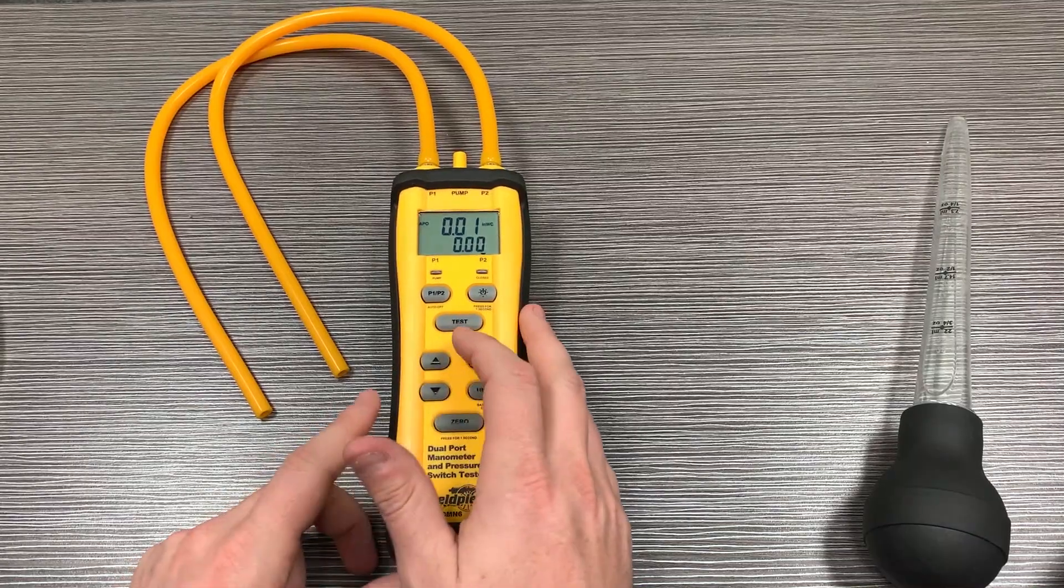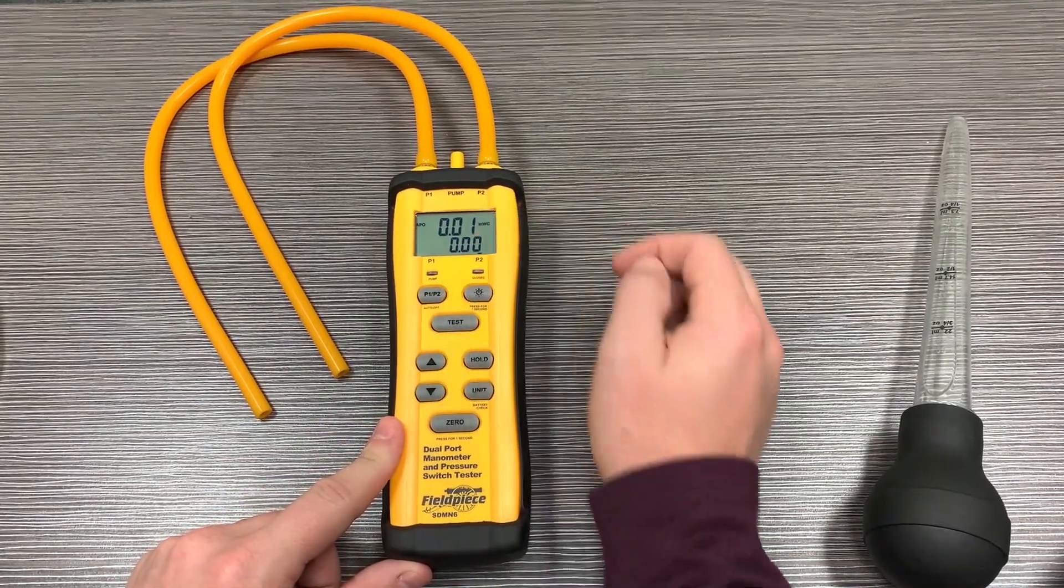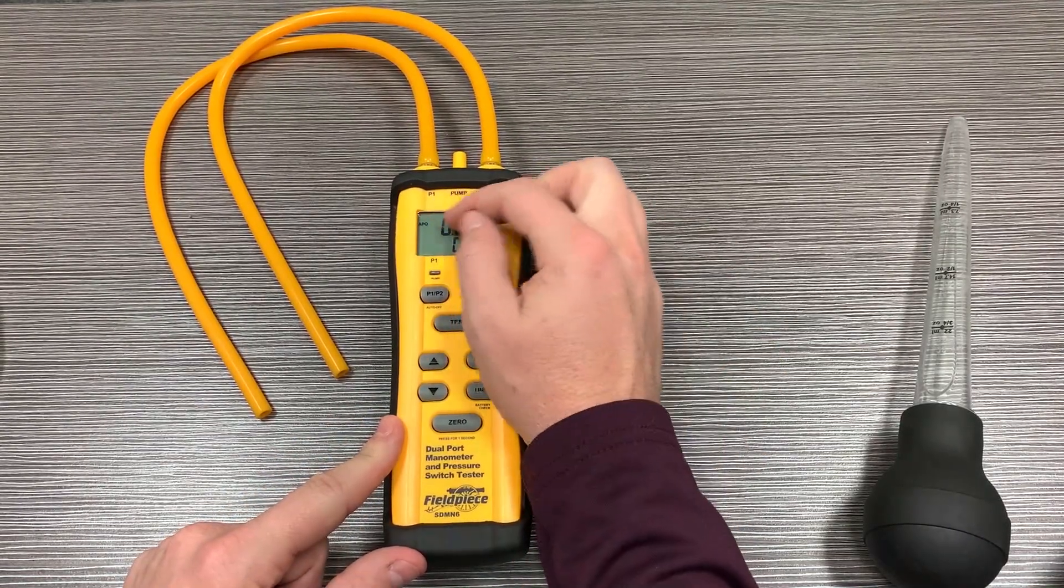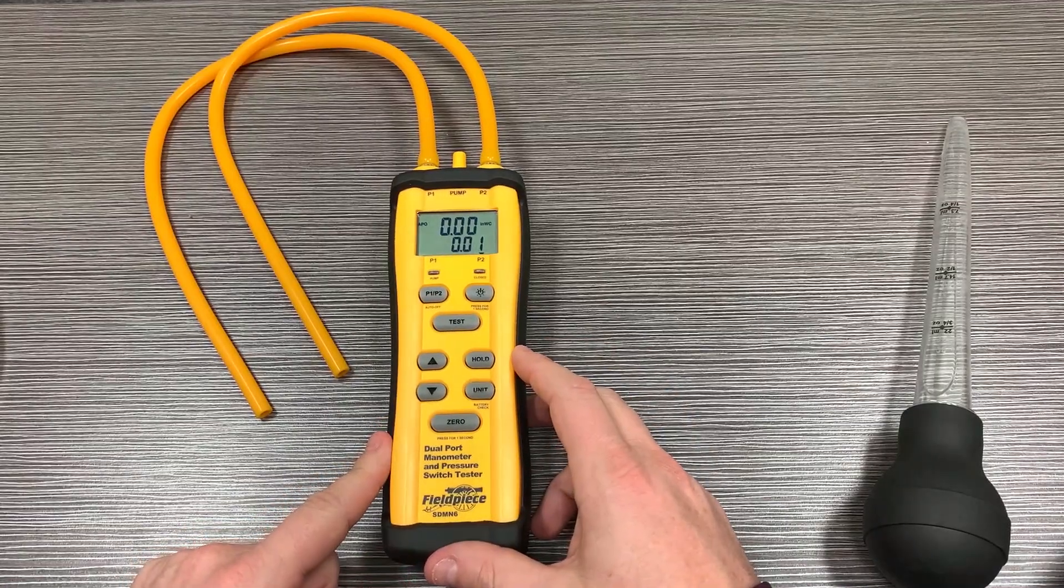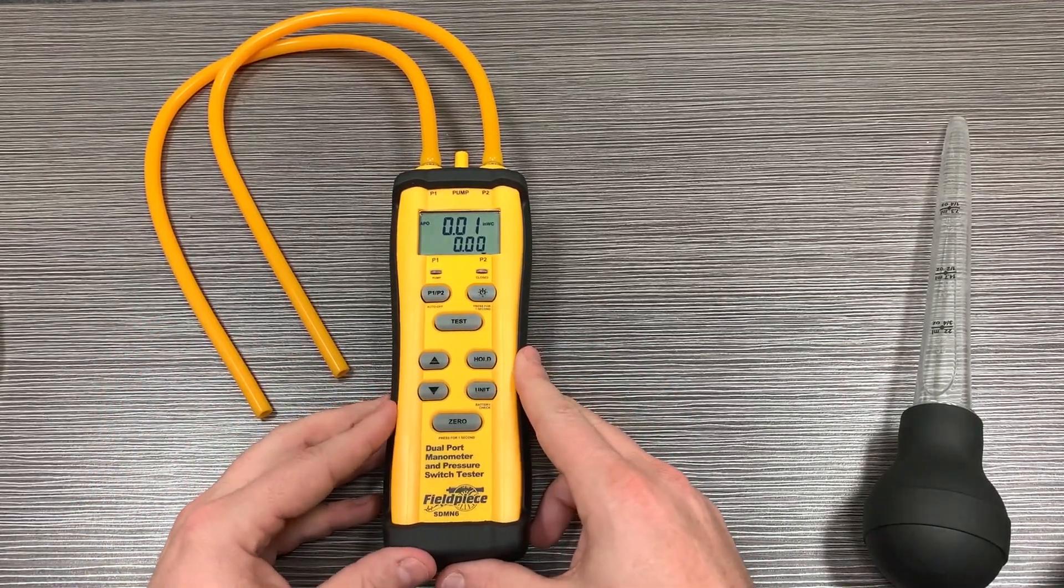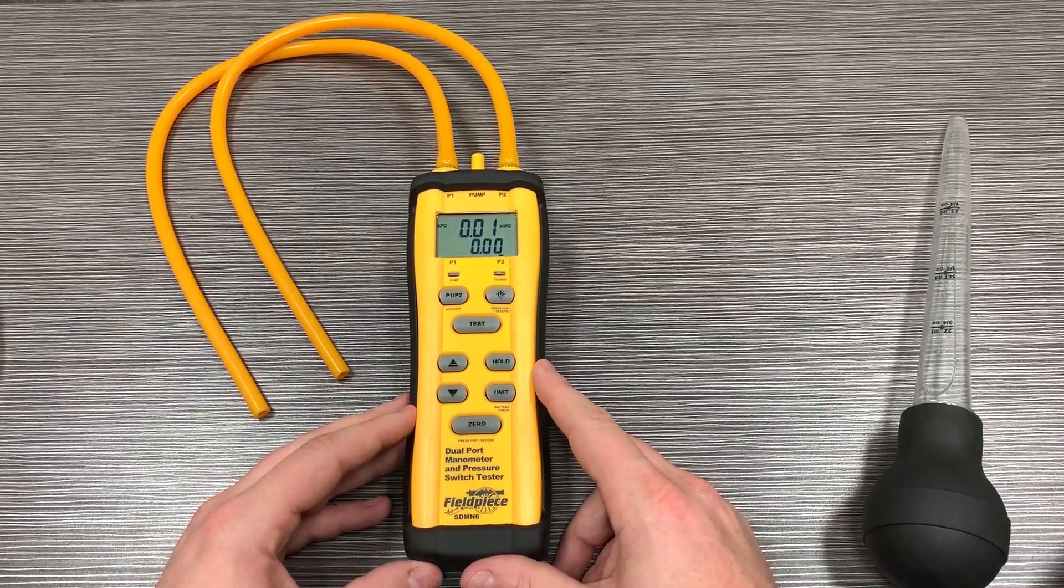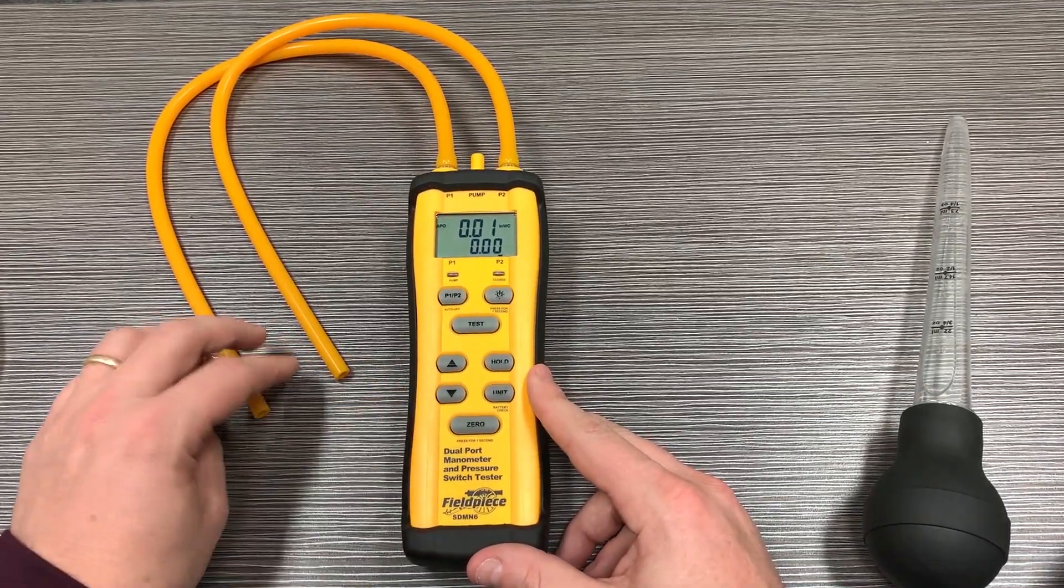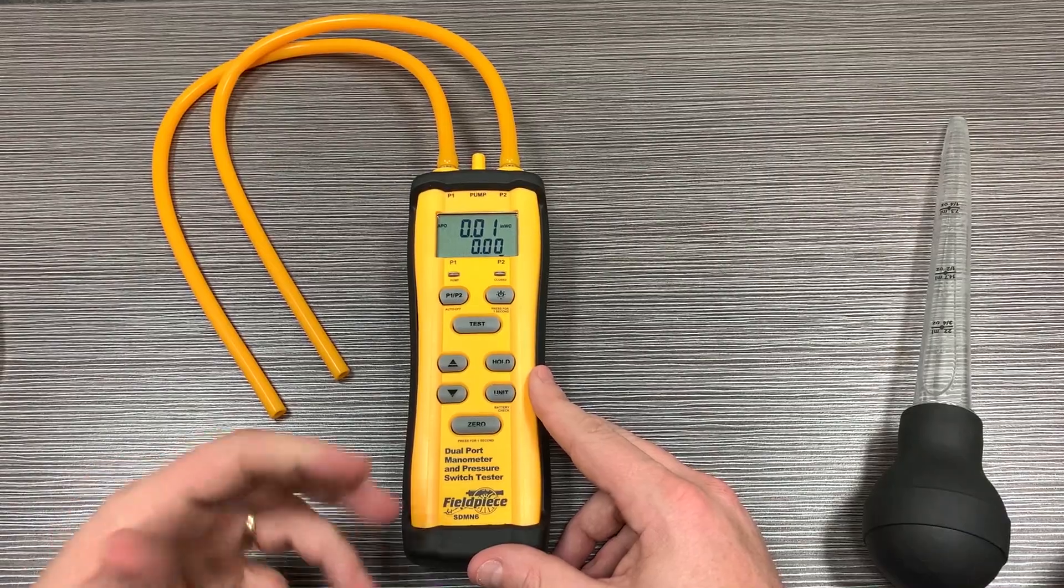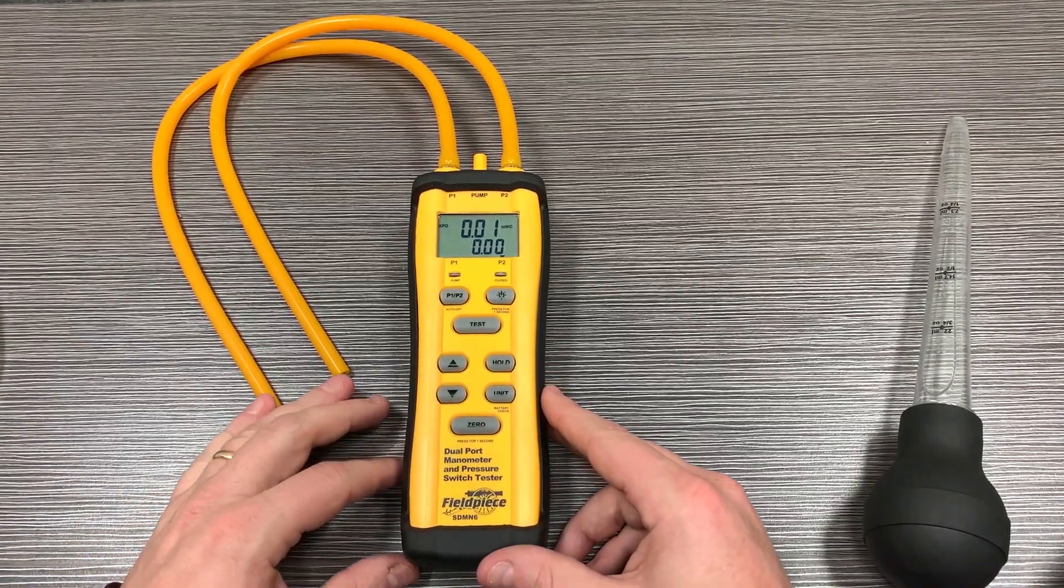The delta P doesn't mean much, so you're not going to care very much about what this number is on a gas valve. You're really going to care about this top number here. There are some gas furnaces, like some high-efficiency furnaces where the gas valve is outside of the combustion chamber, where you actually have to reference one of these tubes to the combustion chamber in order to set the gas valve accurately.